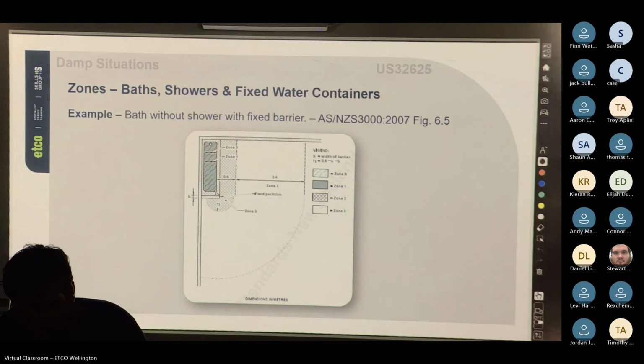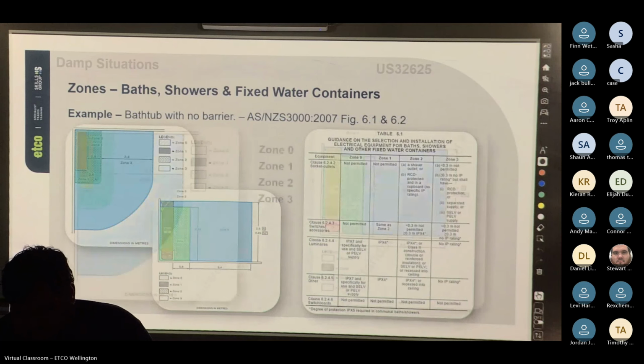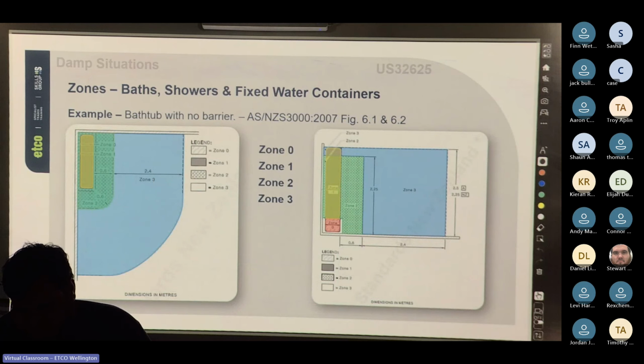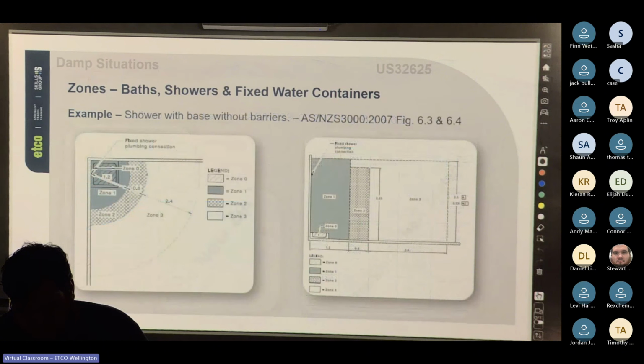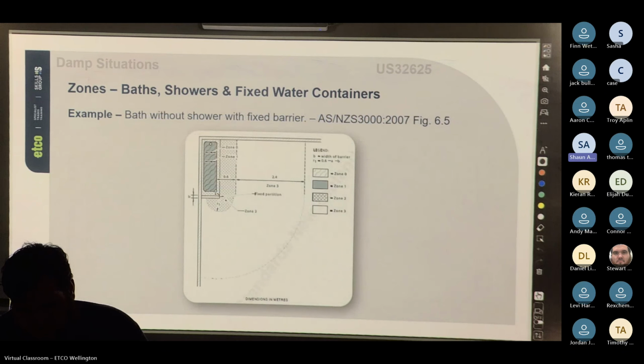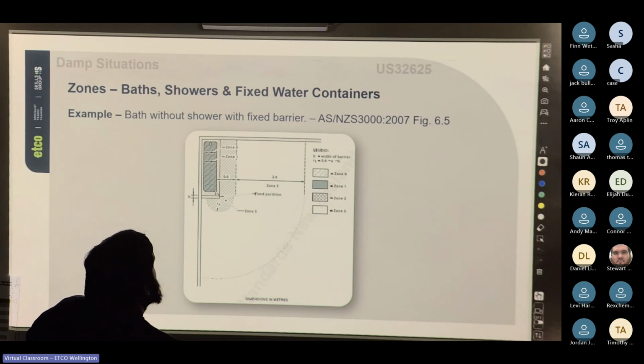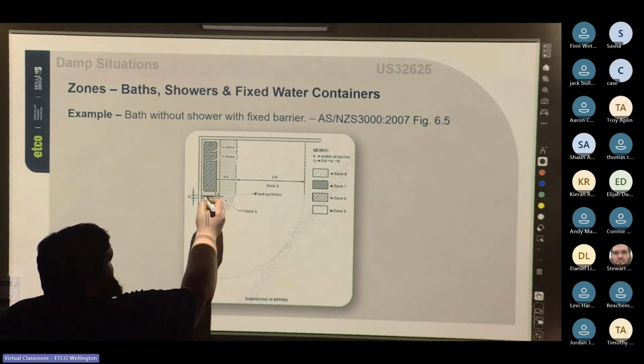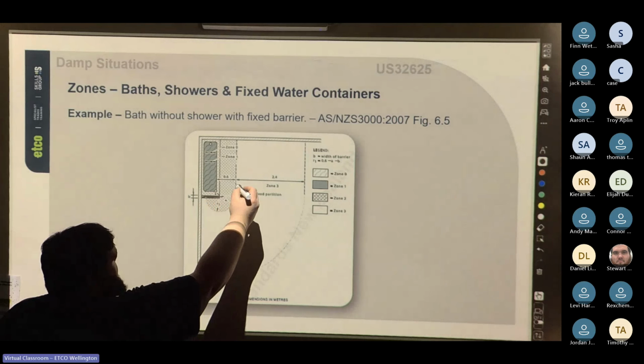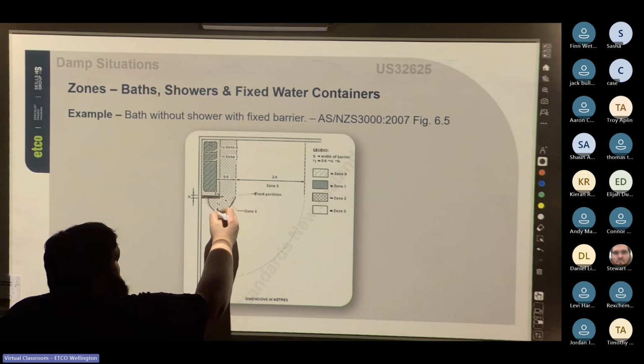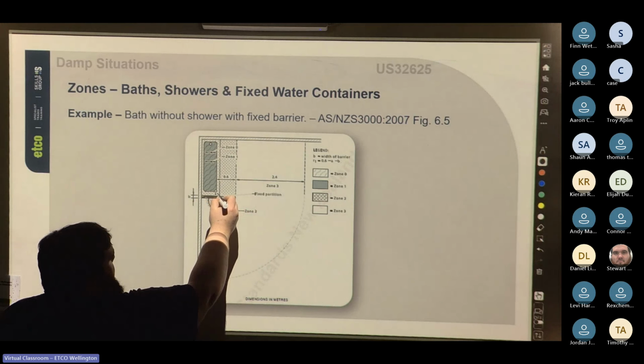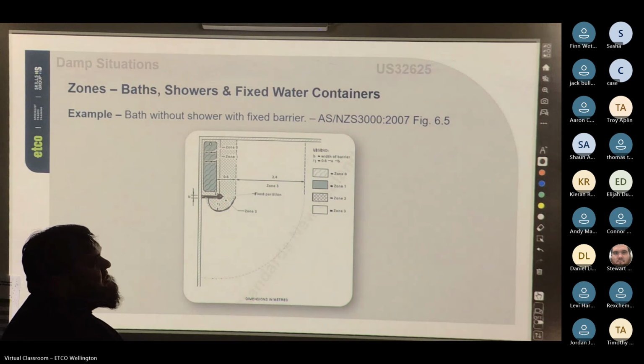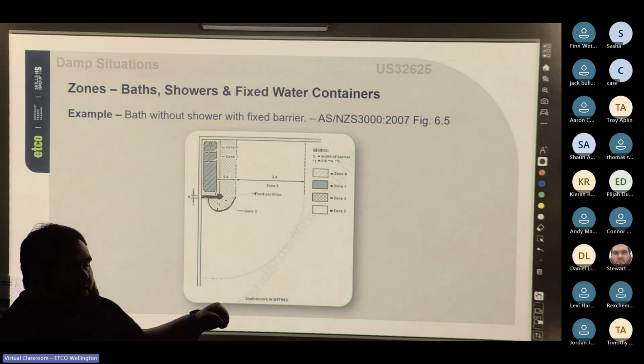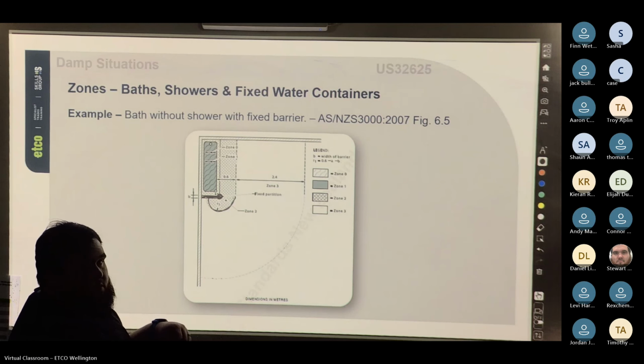The diagrams are different. So 6.1, if we go back to it, is a bathtub with no barrier. So it's a bathtub without a shower head, without a barrier. And then if we go to 6.5, it has no shower, but it has this fixed barrier at the end here. So it changes the dimensions of zone 2. So it has a curved area around the end of the barrier. So we can use that corner of the barrier as a pivot point to draw out our zone 2. Oh, gotcha.